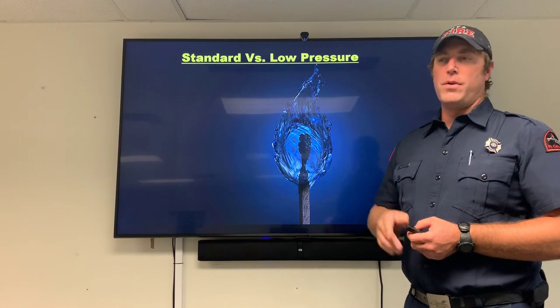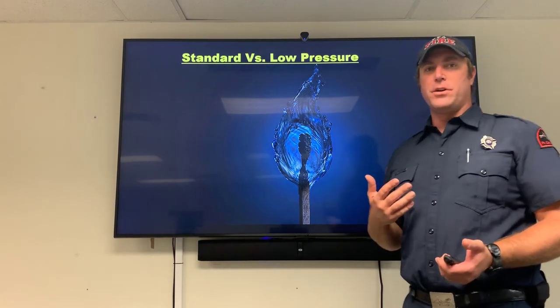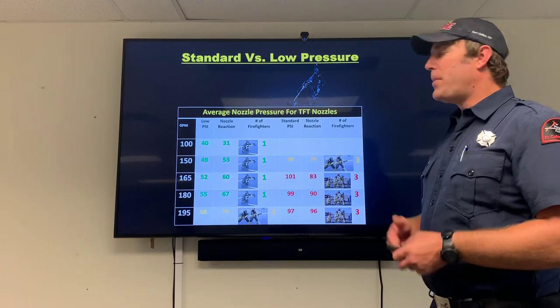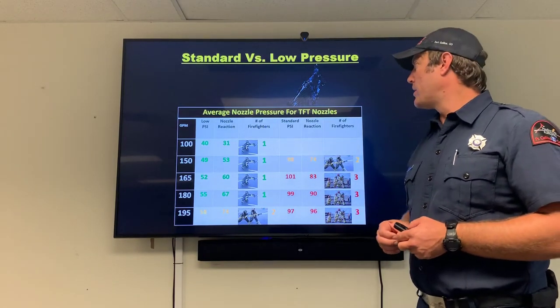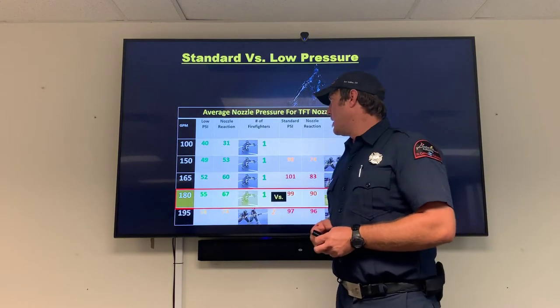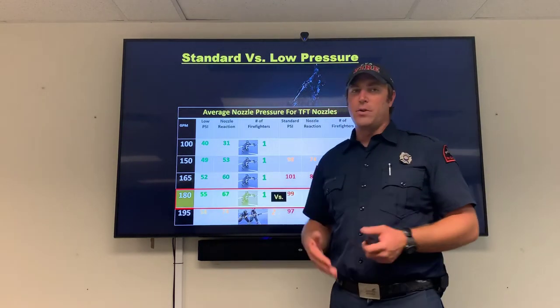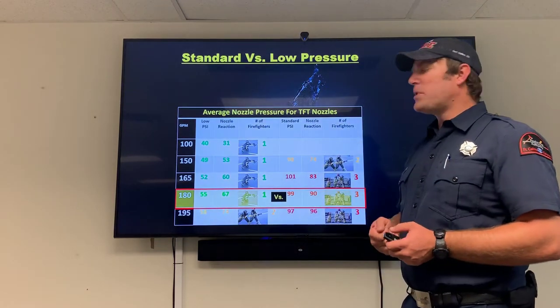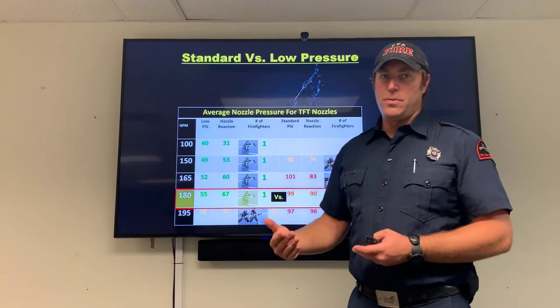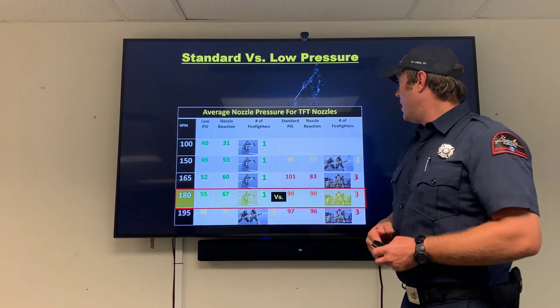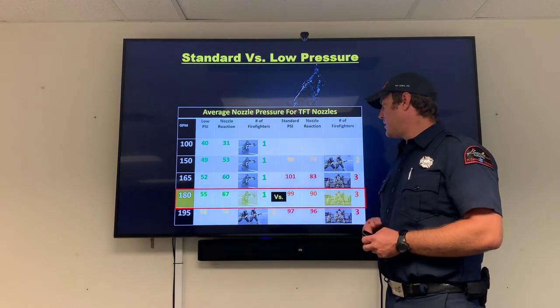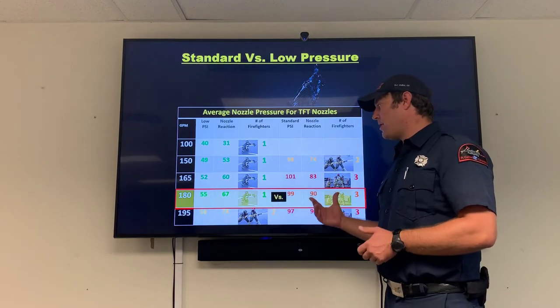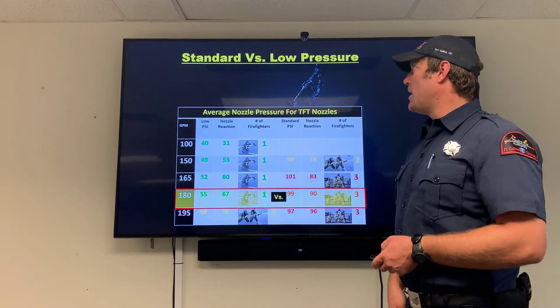Looking at the difference between standard and low pressure: this was the slide used in 2016 during the major emphasis training to convince the department to go to low pressure. The biggest effect is nozzle reaction. At our target fire flow of 180 GPM in low pressure, we achieve that with 67 pounds of nozzle reaction — under the 70-pound target, manageable for one firefighter. In standard pressure, to get the same flow we'd need 100 PSI at the nozzle, giving 90 pounds of nozzle reaction. We've essentially taken a one-firefighter line and turned it into an almost three-firefighter line.